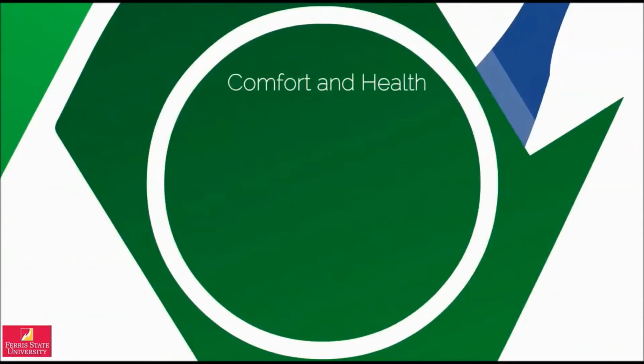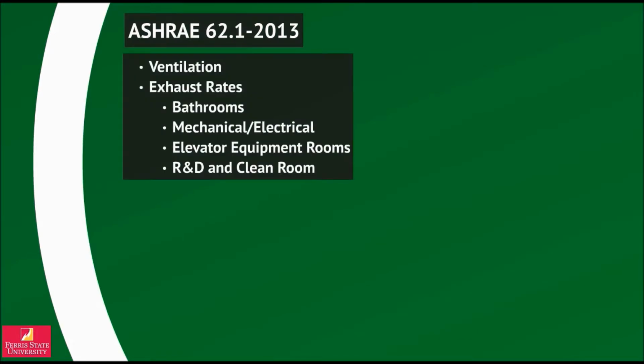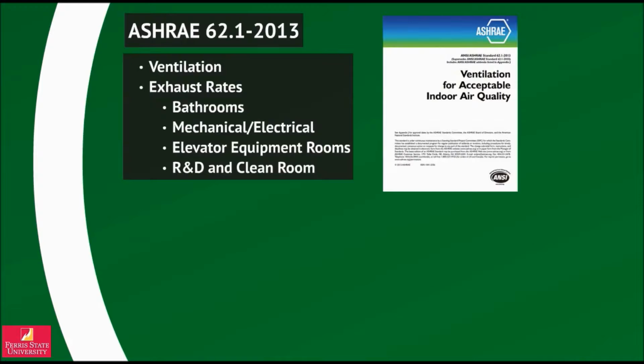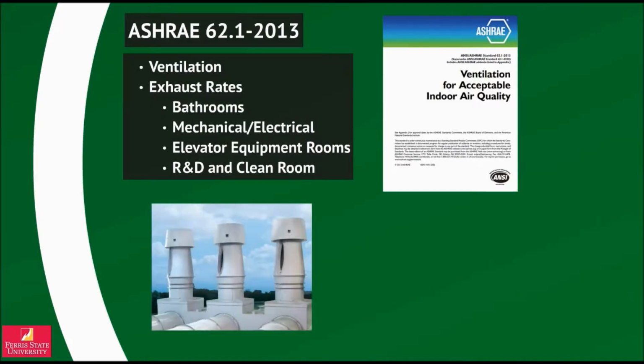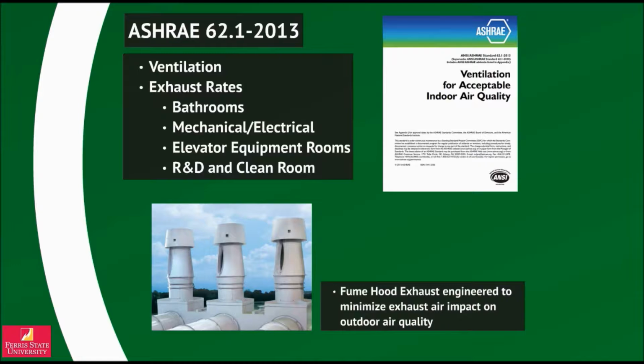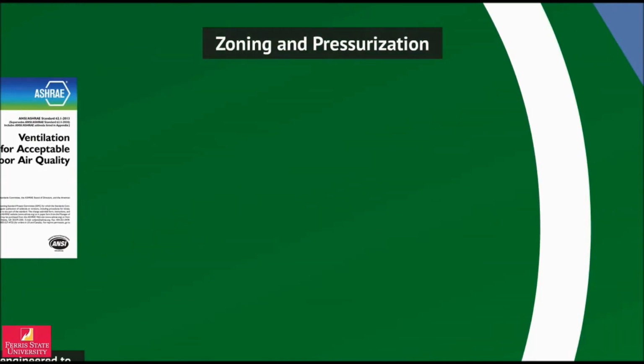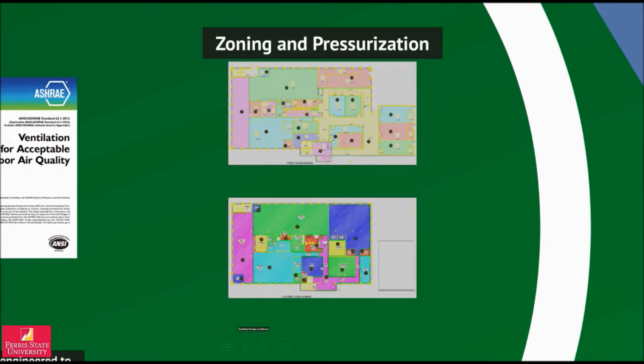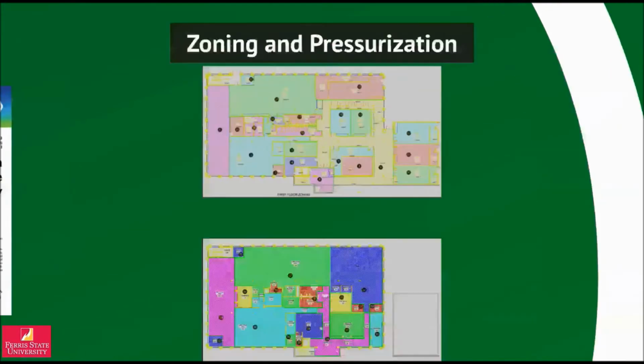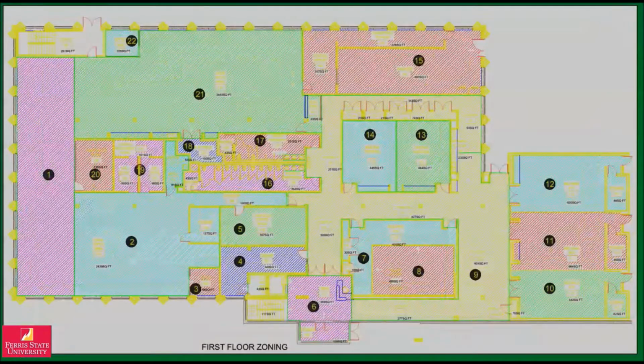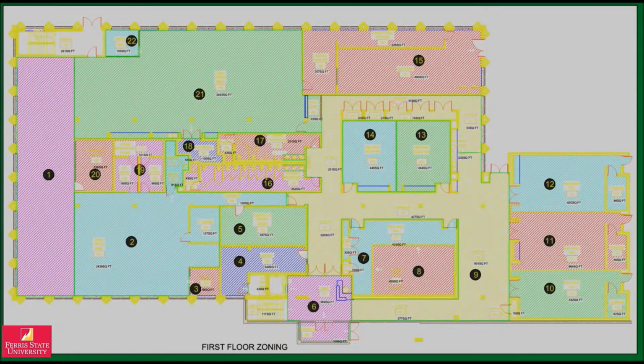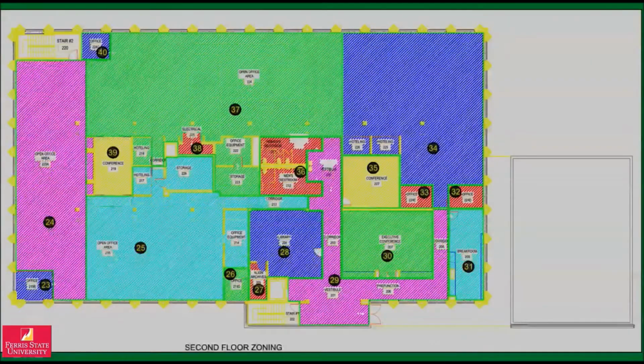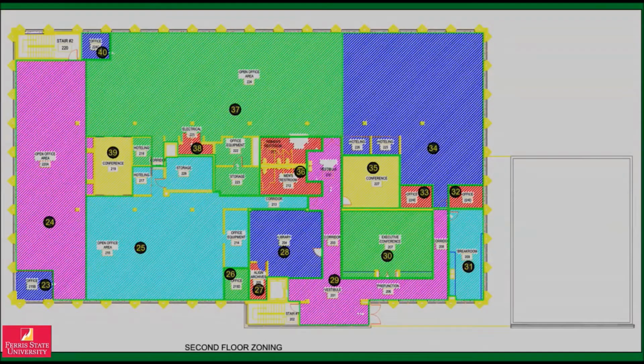To ensure that proper ventilation and exhaust rates were provided to each space, ASHRAE Standard 62.1 was utilized to determine the minimum requirements for acceptable indoor air quality. The exhaust rates for the R&D areas were obtained from the owner's specifications regarding the lab hoods within them. Zoning and pressurization played a major role in the design. These two diagrams display both floors and the proper zoning boundaries. Space type, size, orientation, temperature, and humidity requirements were used to determine each zone. Pressure requirements in each zone were dictated by the function of the space.